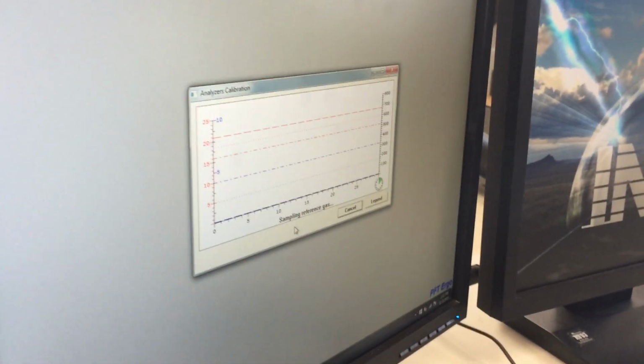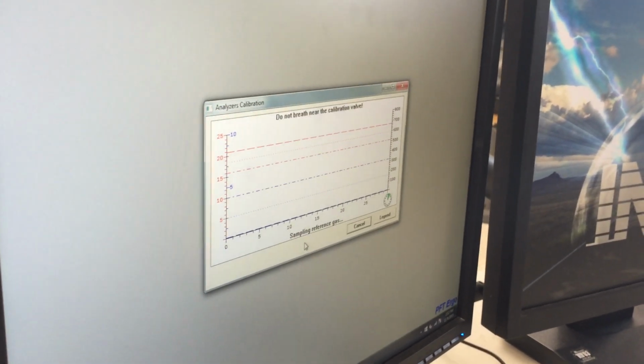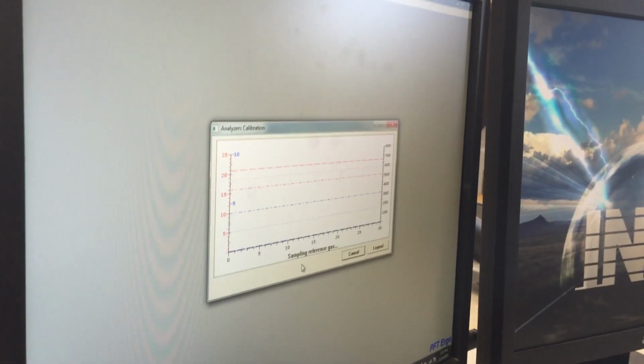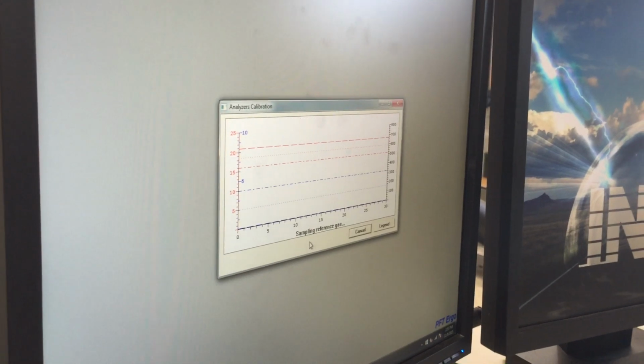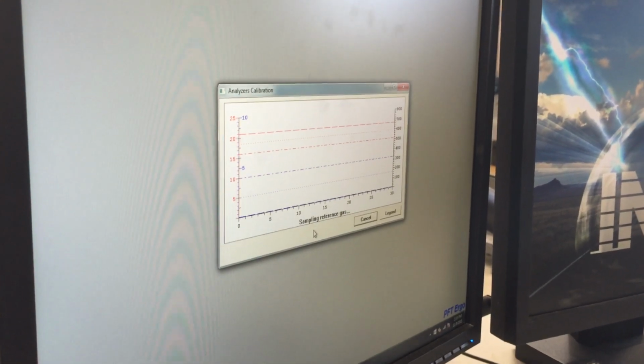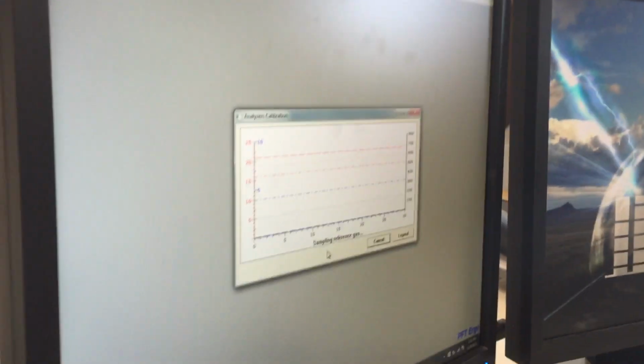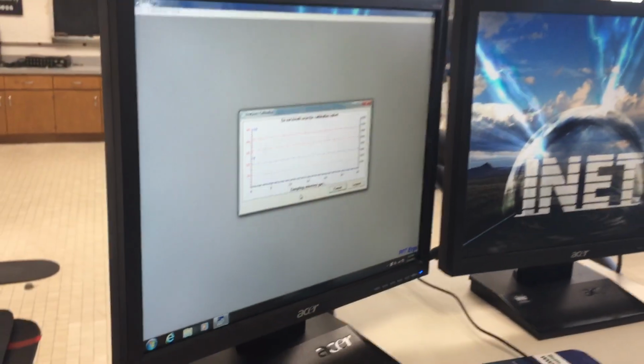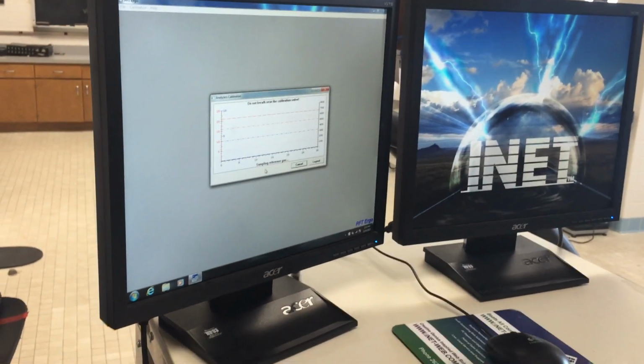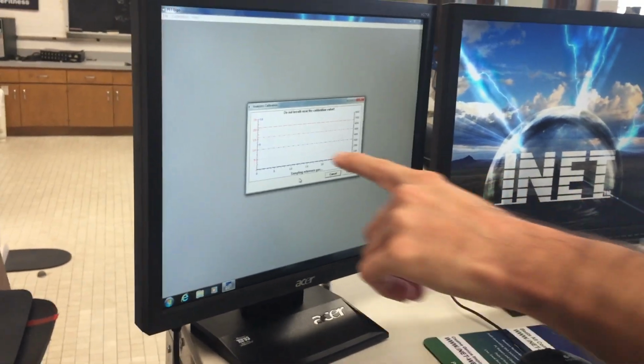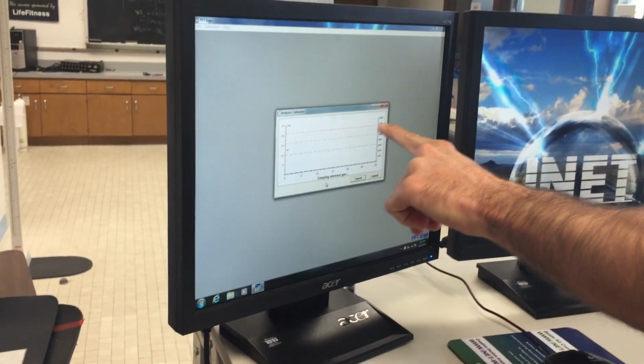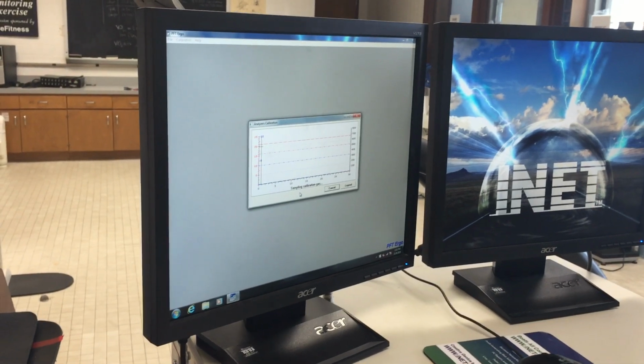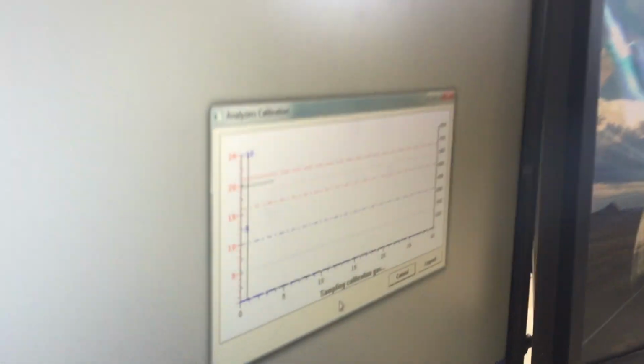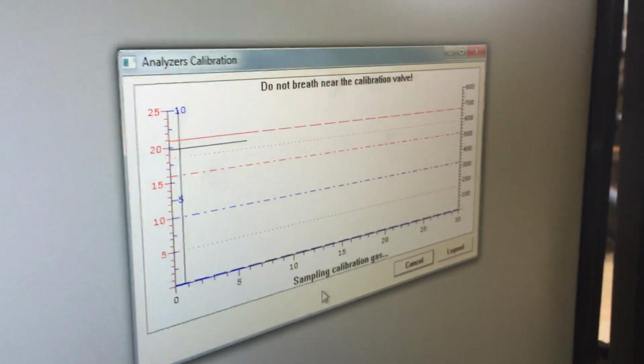And it's going to say, you can see it, do not breathe near the calibration valve. Essentially, you try to step away from the machine at this point. If you're talking or there's too much going on near it, it can read your breaths as part of the natural air. It can cause a little bit of error or variability in the sampling rate. So at this point, we are just allowing the computer to do its own thing. Eventually, we will start to see a black line coming across the top of the screen. It'll come right around here. That'll start in just a few seconds. There it goes. When that black line gets all the way across, the sampling will be complete.